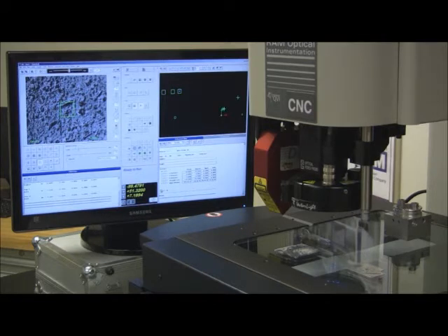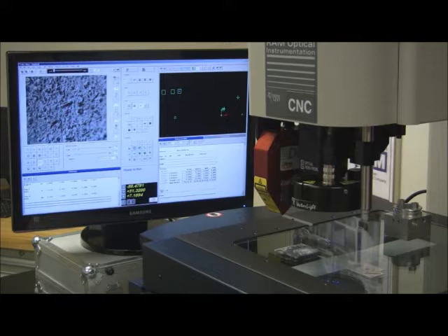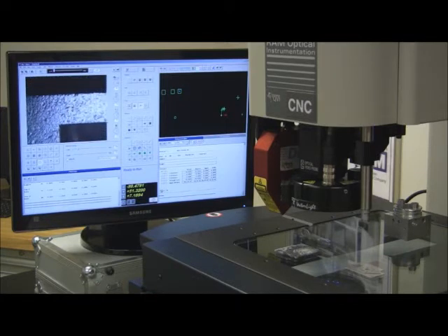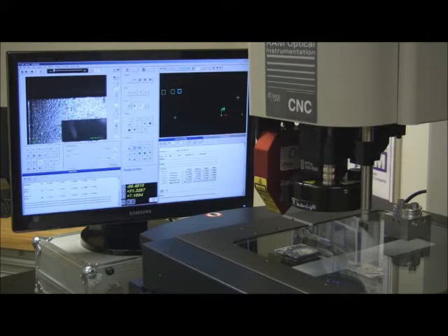Right, to go down and measure with the laser now, I'm going to go back to low mag so we can see the part. Alright, I'm going to select the laser target, and right now we're set on a laser scan. I can do an arc scan, a circular scan, or a box scan. Where you might use a circular scan would be if I was measuring the top of a bottle. And the top of a bottle is a sealing surface. So the flatness is critical. If the top isn't flat, then when I screw the cap on, it's going to leak.